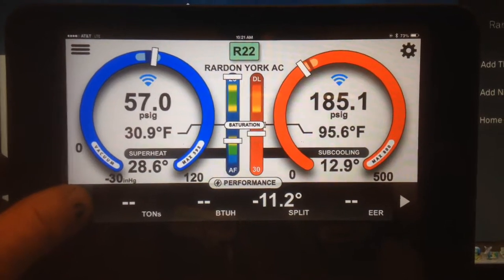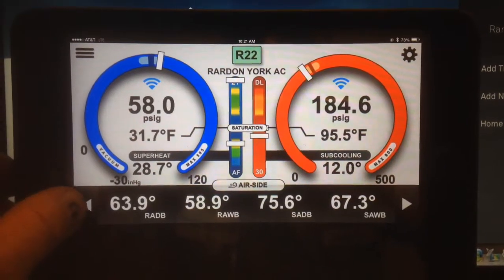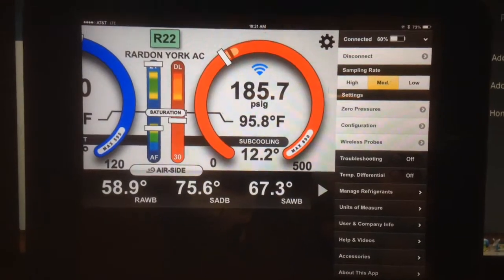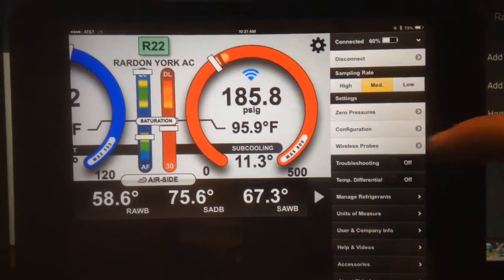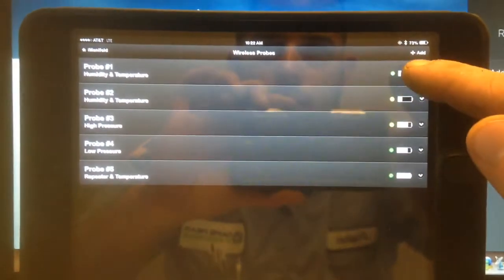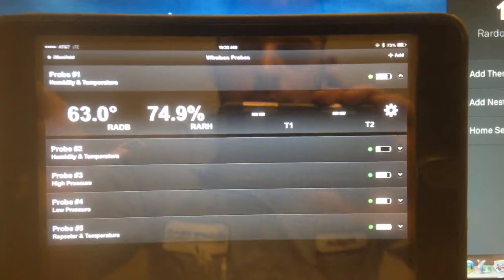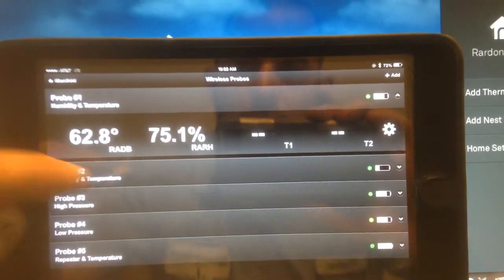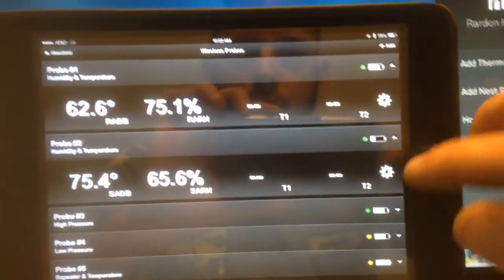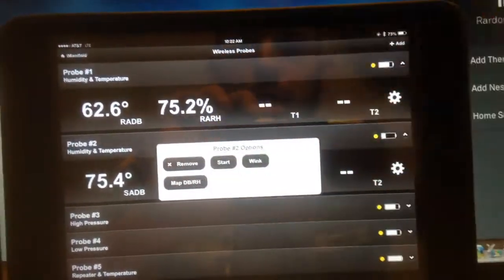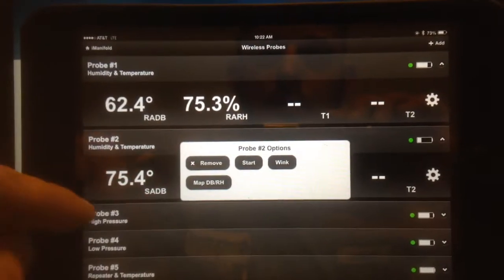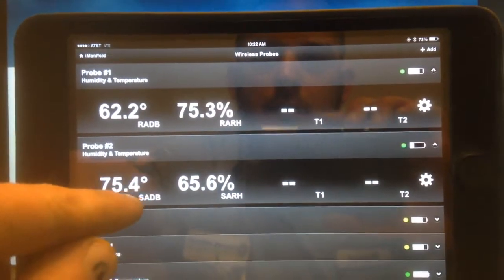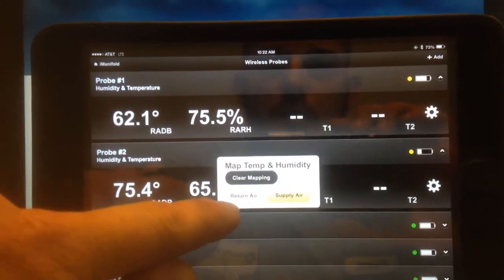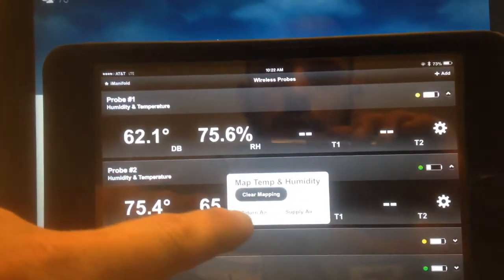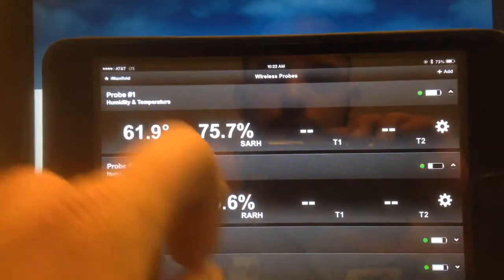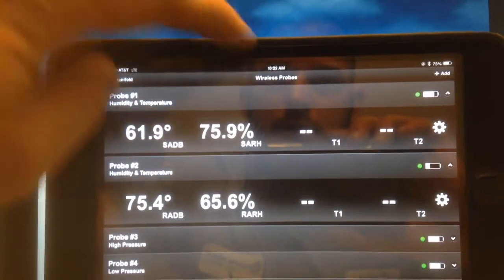Just for fun, it looks like I've got my supply and return backwards. So we're going to go back over to the wireless probes. We're going to take the probe 1, which is set up as return at this point, but obviously wrong. And we are going to remap as supply air, and then remap this as return air. So now we should see that information properly.